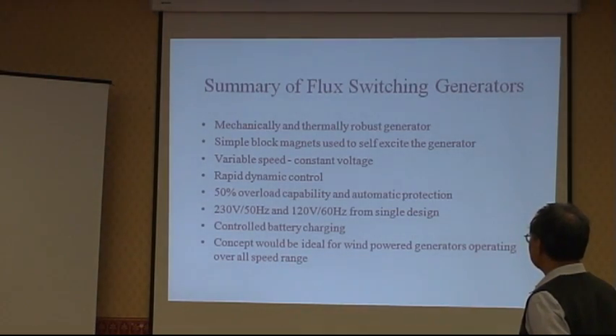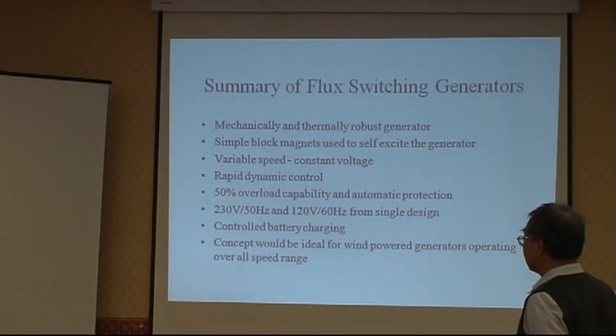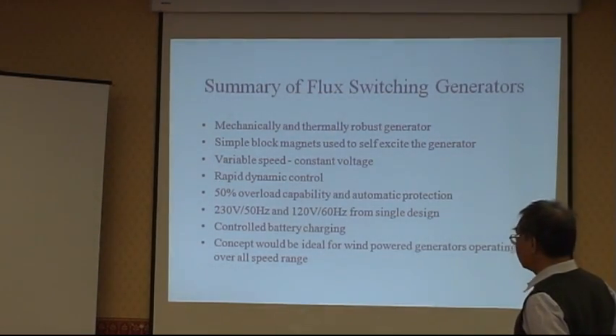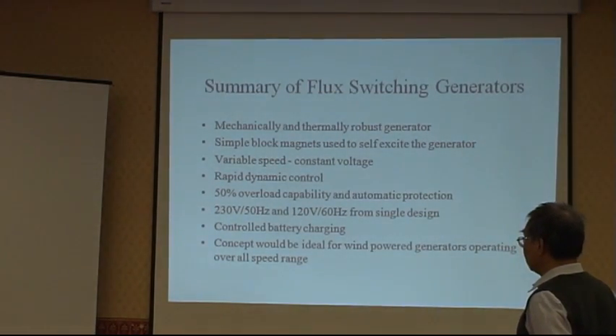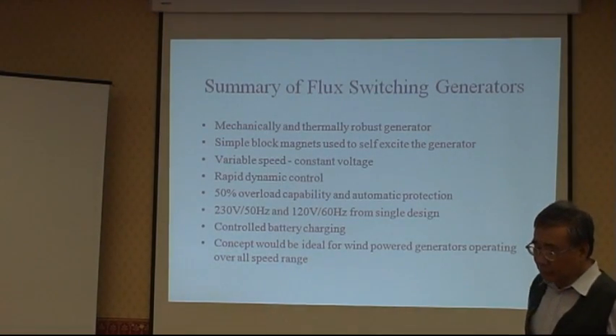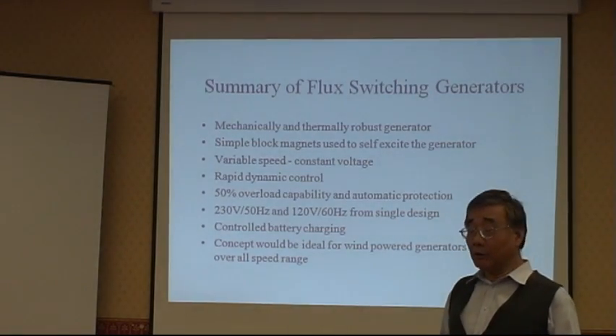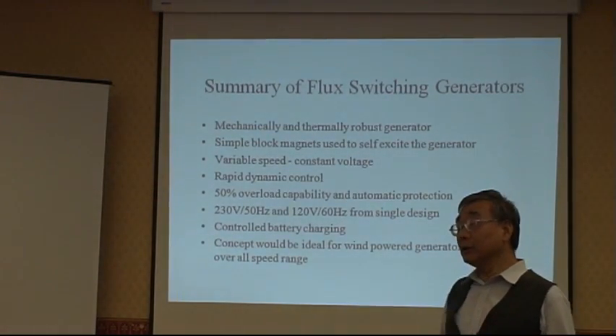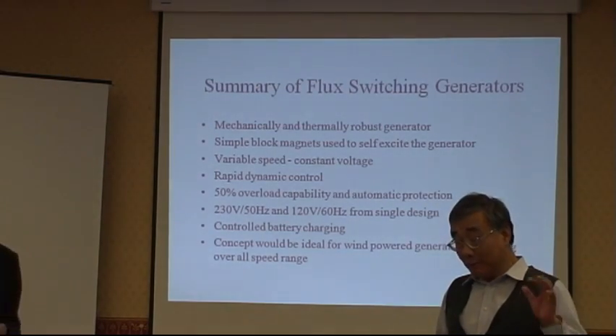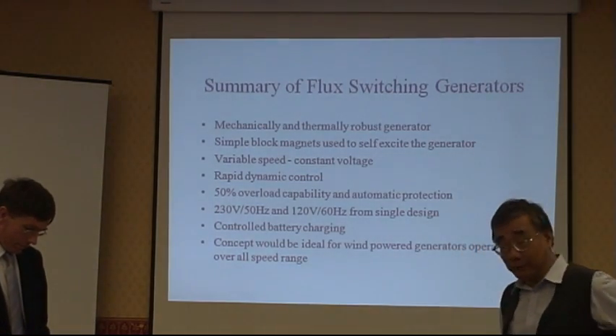Now, this machine, our prototype is a gasoline engine, but it would also be suitable for wind power generator, because the speed range of wind powered machine is very wide, so the field control gives us constant voltage over wide speed range.